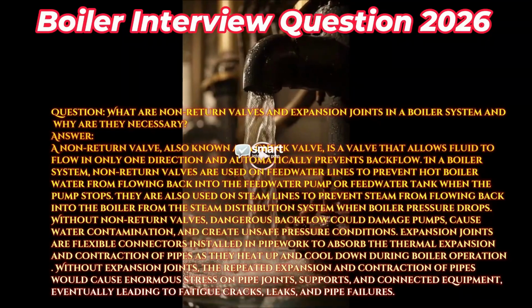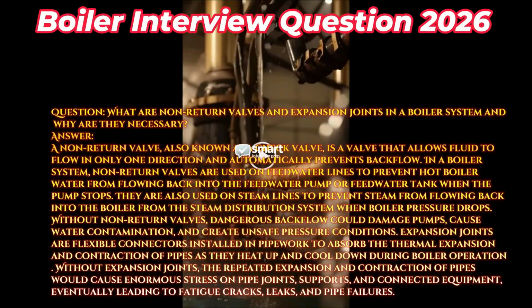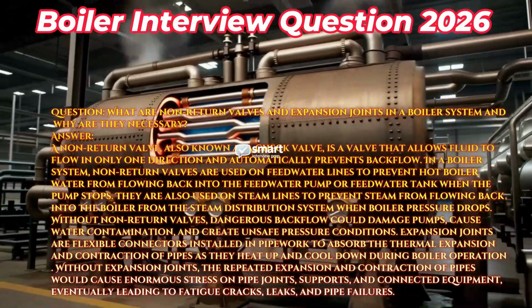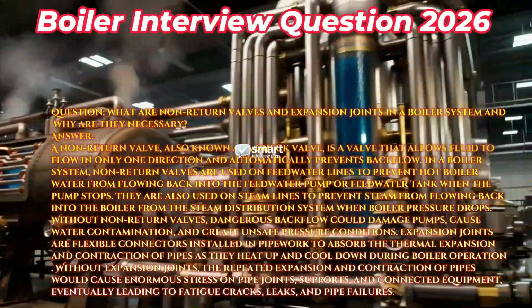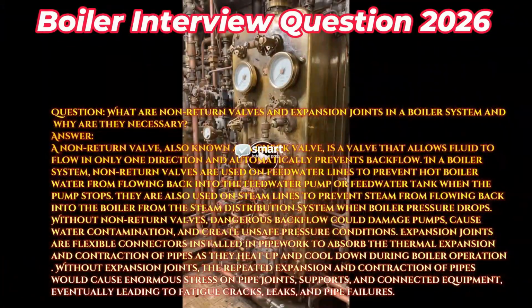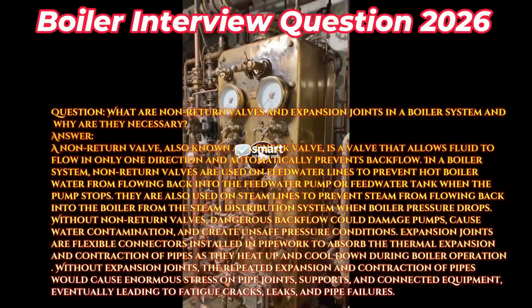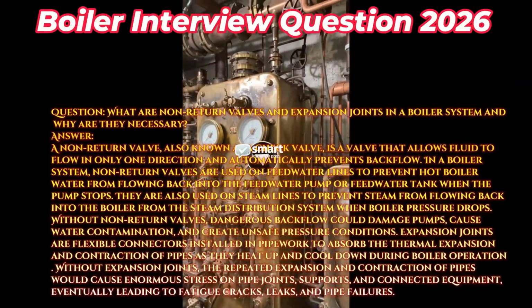They are also used on steam lines to prevent steam from flowing back into the boiler from the steam distribution system when boiler pressure drops. Without non-return valves, dangerous backflow could damage pumps, cause water contamination, and create unsafe pressure conditions.